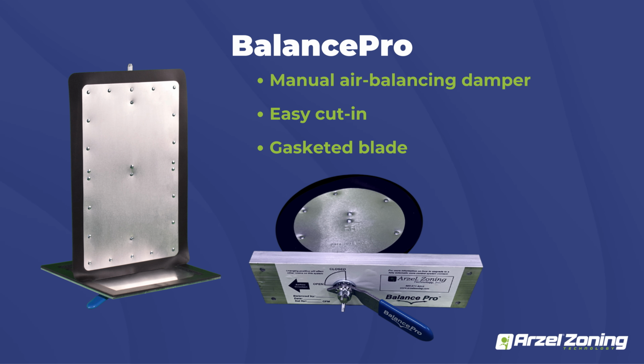But also it's got the same template as all our other dampers, so you don't have to pull the ductwork apart. You can cut that hole, insert the damper, and you're good to go. And say you got a customer that you did balancing for, you installed a bunch of these, you balance that home, and then 2-3 years down the road, they decide, hey, I want to do traditional zoning in my home. You can remove these dampers, and our current dampers will fit directly in the slots that you already cut. So you don't have to worry about making the holes any bigger. It fits in that exact same footprint.